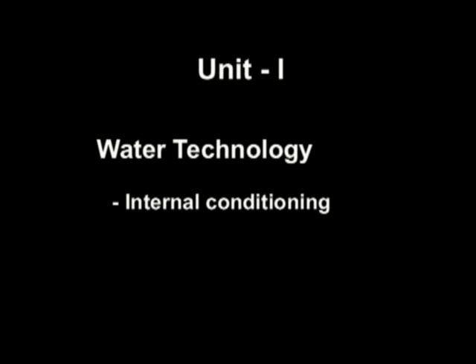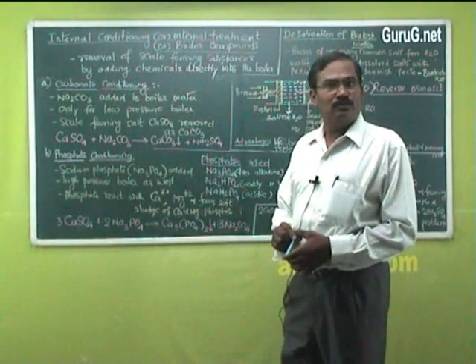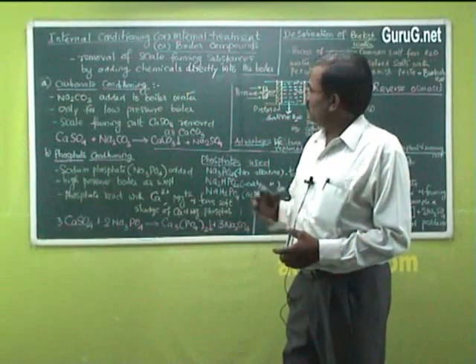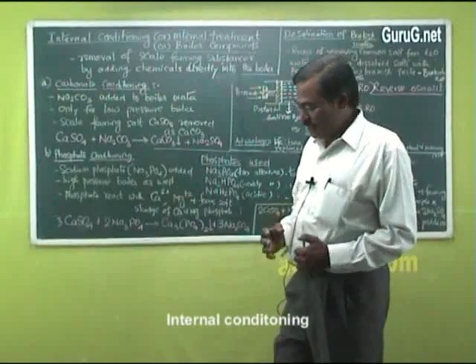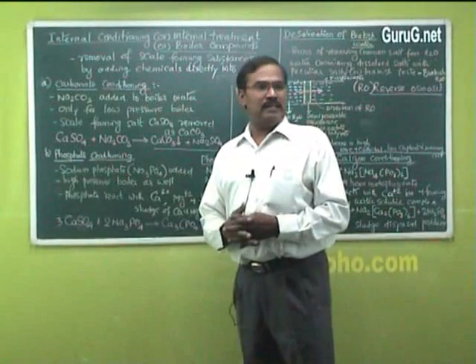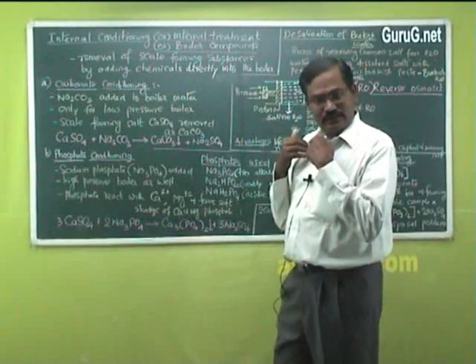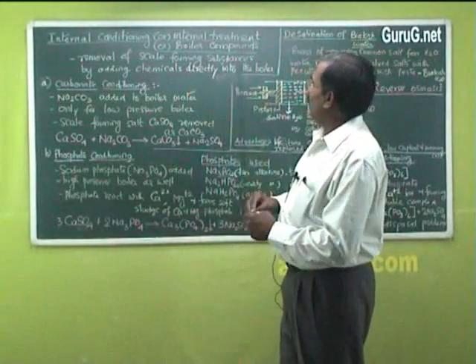Softening of water can be carried out by two major processes. One is external conditioning and the second one is internal conditioning. In external conditioning, we purify the water before it is fed into the boiler. But in internal conditioning, the raw water is simply fed into the boiler, and chemicals are added into the boiler which remove the scale-forming substances. That is the major difference.